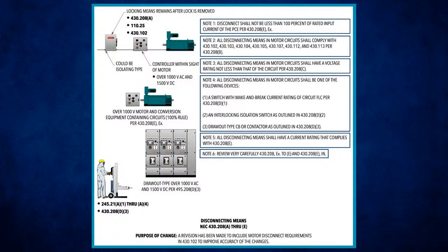That's just a couple things they added in here, but the main part is they refer you back to all the other sections that deal with disconnecting means. The two most important are 430.102 and 110.25, but they also mention other spots to look at, like 103, 104, 105, 107, 112, and 113, if I'm not mistaken.